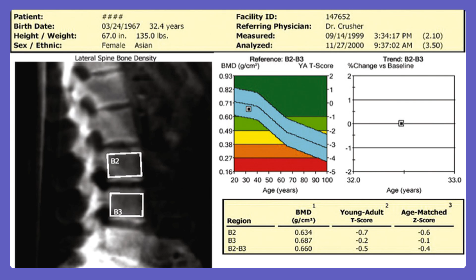So DEXA scans has to do with precision and accuracy. This is very similar to a lot of other QA/QC type measurements. Two terms that are used in DEXA are precision and accuracy. Precision is the ability to reproduce the same result when repeated in an identical fashion. You compare it to other scans. Accuracy is how well it reflects the true or actual value of the object measured.